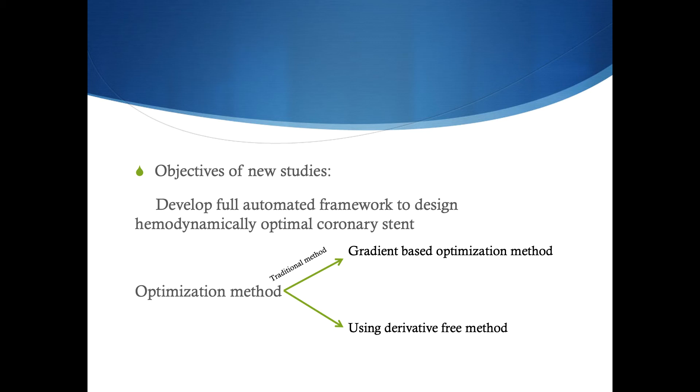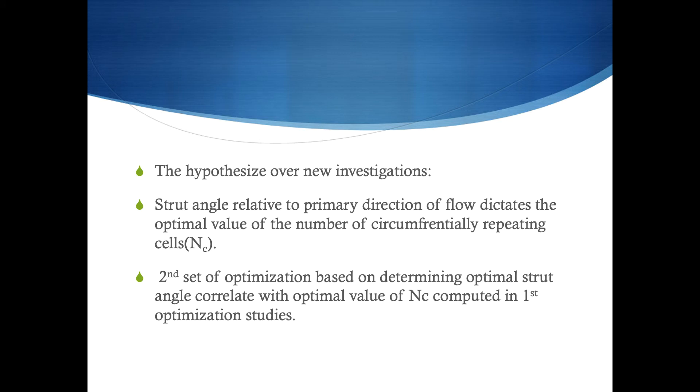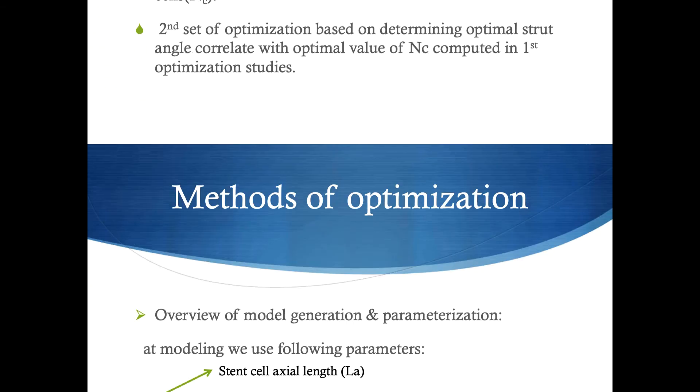The gradient-based optimization method and derivative-free method help us develop an automated framework to design hemodynamically optimal coronary stents. The hypothesis says that the strut angle and primary direction of flow has an optimal effect on the number of circumferentially repeated cells. The second set of optimization is based on determining the optimal strut angle correlated with the optimum number of cells computed in the first optimization method.